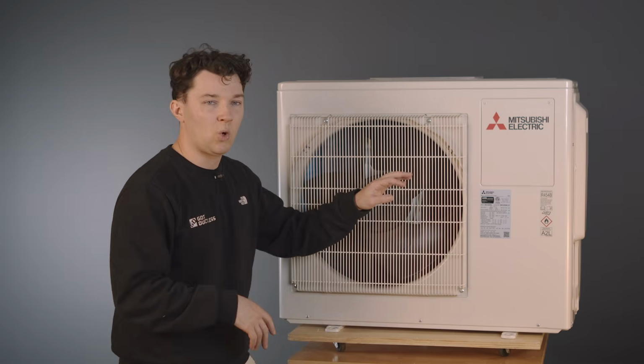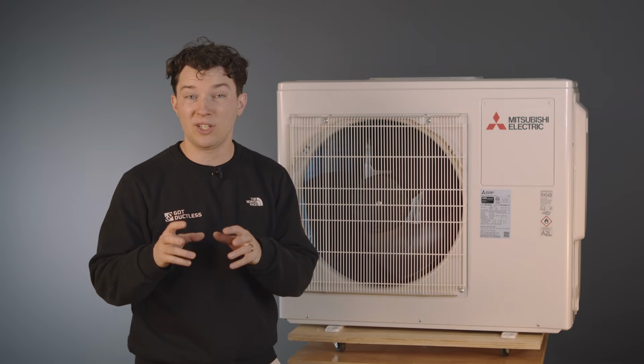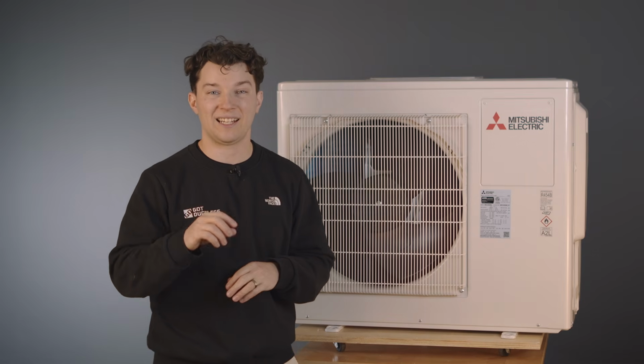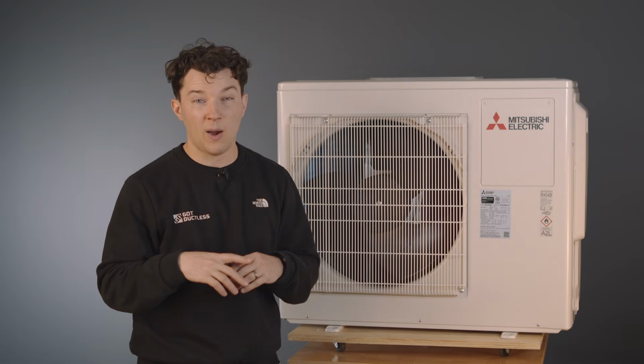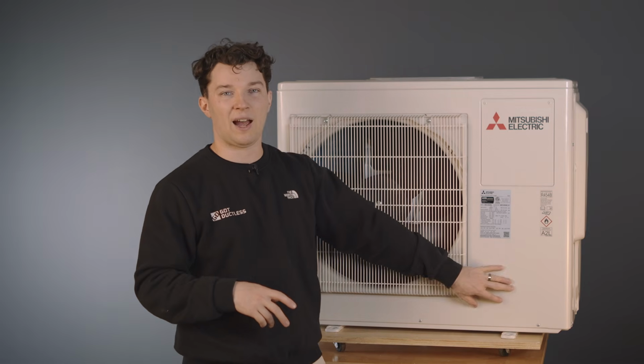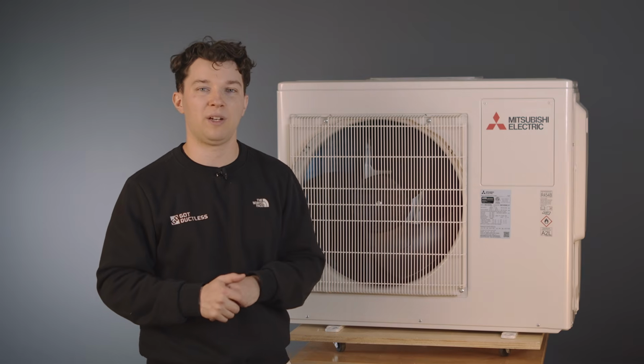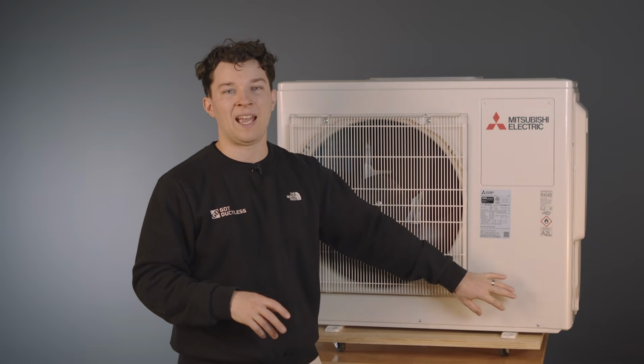This is a 1/4 and 3/8 connections, and so if you're installing a 15,000 BTU, maybe mixed with a 6,000 BTU, which equals 21,000 BTUs, which is compatible with this outdoor unit, you're going to have 15,000 BTU, which has 1/4 and 1/2 inch line set connections, which then you would have to port adapt here at the outdoor unit from 3/8 to 1/2 inch as a step up, and then you run 1/4 and 1/2 inch line set to your 15,000 BTU air handler. However, let's just say you're running 2 9,000 BTU indoor air handlers off of this outdoor unit, then you don't have to use any port adapters, you just run it directly to this outdoor unit here.